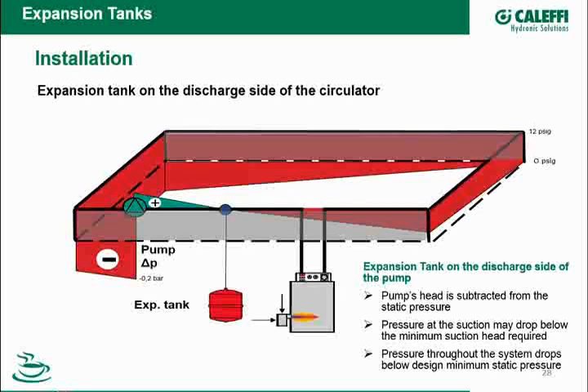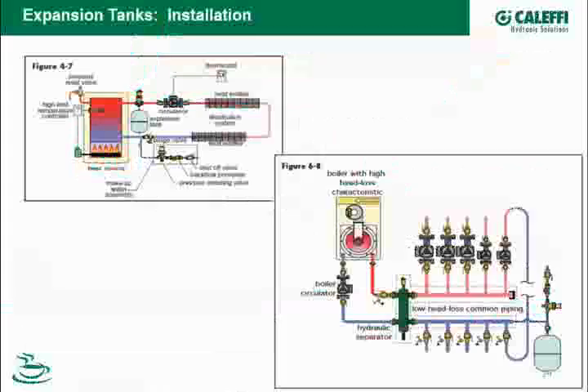So from the design side, what we like to see is something like these two drawings out of idronics 12. Figure 4-7 in the upper left-hand corner: direct connected boiler to system. So here's my boiler, here's my expansion tank, here's my circulator. Point of no pressure change is locked in here.